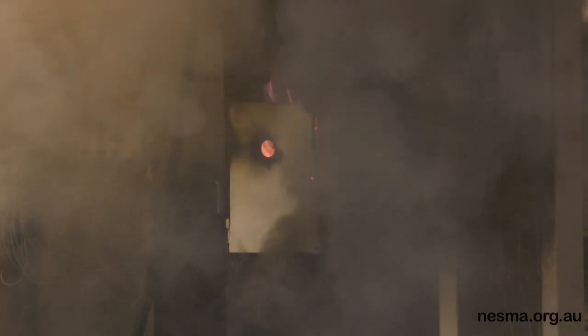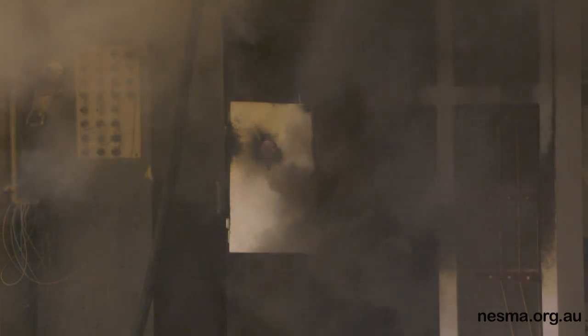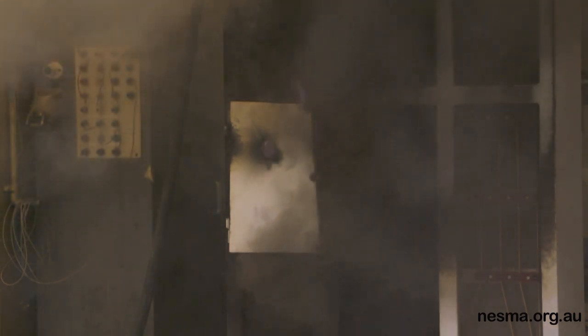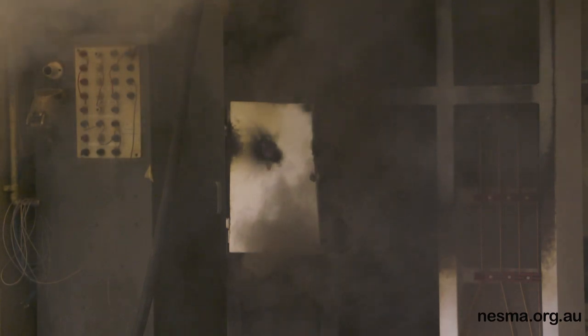Somewhere it might be a plant that's creating a dust that's conductive, and that also could lead to a line side propagation of a fault. Here is a perfect example where the assembly constructed met all the requirements for a standard test, but when we put the board to see how it would perform with component failure, then we had this quite drastic effect.